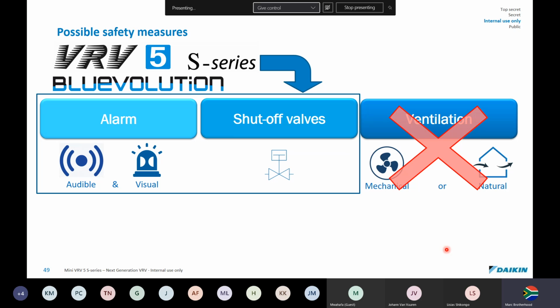What Daikin decided to do was to not use any third-party mechanical ventilation. Instead, we have put alarms in the indoor units that go in the rooms, which are audible. So your remote control will start beeping and making a buzzing sound. The remote will also show a red ring, and it'll also tell you that there is a leak. Further to that, the outdoor unit will shut down. It'll do a liquid line shutdown on pump down valves.